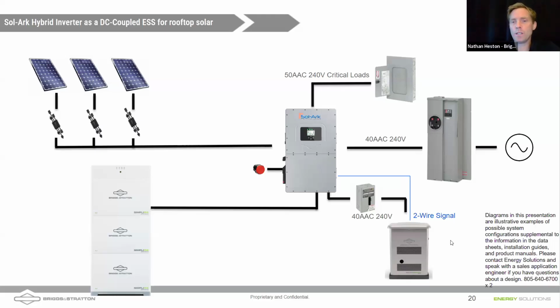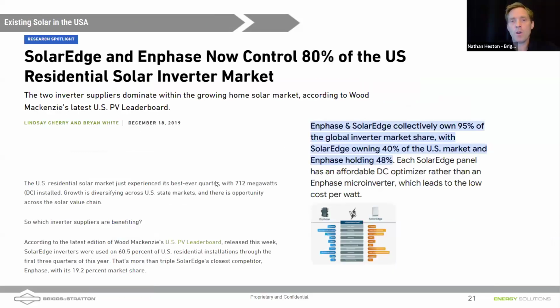And we're also showing that this inverter can integrate a generator, right? So we're showing here that we've got a generator with a 2-wire signal to start. And so in a grid outage, this inverter, if there is no solar power and the battery state of charge is getting low, this inverter can start up a generator, cover the loads, and charge the batteries.